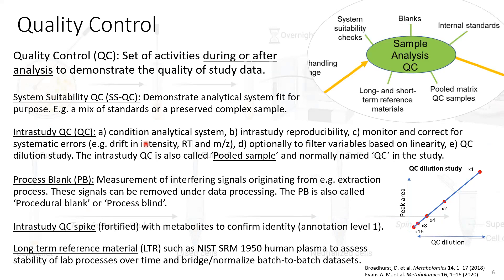Quality control is something we do during or after the analysis. One of the things is the suitability test, which demonstrates if the platform is good enough. What we typically do in our lab is have a standard spiked into a matrix with at least 50 different components — metabolites or pharmaceuticals. We run that on the platform and check if the retention times are good enough, the mass accuracy is good enough, and the intensity of the metabolites. If it fits and it's good enough, then the platform is ready to use.